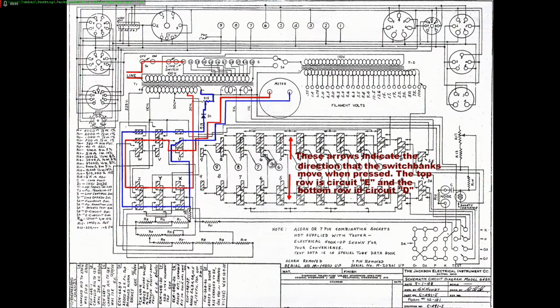These switches, if you notice, are the same switch, different segments of that switch, but they all move together. The top ones are row E, circuit E, and the bottom row is circuit D on the front panel. So when you depress a circuit E switch, all these segments move together and contact the contacts that have the arrows. So if 6 was pushed, this segment would be all the way up contacting this contact here. The same works with the test switches, the UV, X, Y, and Z.